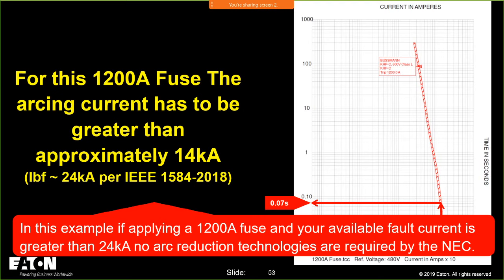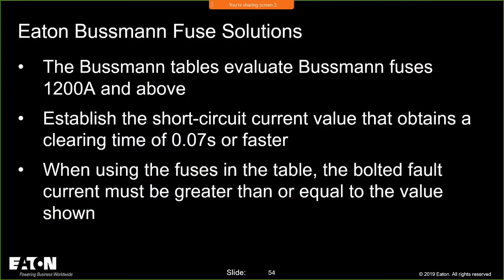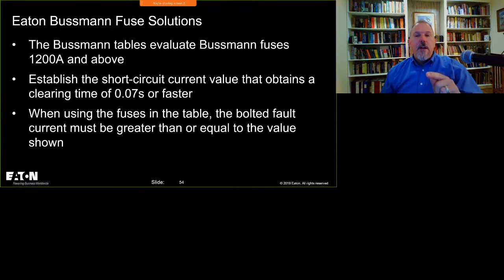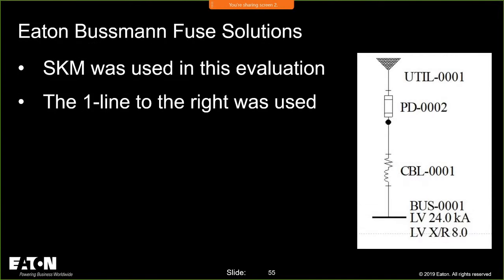Now, again, that's at 480. At 208, you're into a different scenario where you could have a 1200 amp fuse even at these higher bolted fault current values. This is a 480 volt value. So what I'm doing is pulling together tables to help the industry. We have that tool on the market right now, which will do 480, 208, and 600. You guys in Canada got it good because you're at 600 volts. We love 600 volts. You love to push that fault current. You're going to have larger fuses without an arc reduction technology, because that fuse is going to work for you since you're pushing current. You know what fuses eat for breakfast, lunch, and dinner? Never gain weight. The more of it you give them, the more they love it. Current.